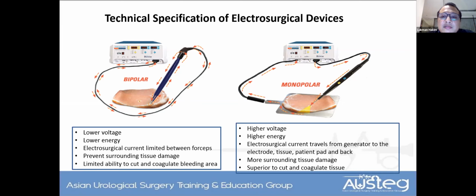However, the advantage of the monopolar electrosurgical device is that it has superior cutting ability and can coagulate the tissue. While the bipolar has everything conversely. It uses lower voltage and energy and triggers a temperature surrounding the tissue of less than 70 degrees Celsius. If we compare to monopolar, it can be 300 to 400 degrees Celsius. And then the main advantage is that the electrosurgical current is limited between the forceps. As we see here, there are no pads that are used.